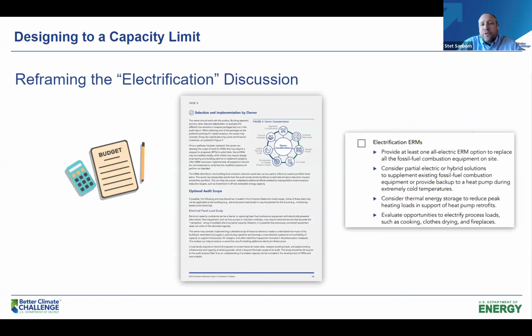And one of the really important ones, and Nora mentioned this, is listed as an optional audit scope of work around the electrical panel. What a lot of folks don't realize is that you may not be using all the capacity that you have on that panel, even if all the breakers are filled up. That's because you may have already gone through a lot of energy efficiency upgrades over the last few years. You might have done an LED lighting retrofit. You might have replaced pumps with VFD controlled pumps in your building. And so you might actually be riding much lower on your capacity curve than you think. You might have additional capacity on that panel, but you won't know unless you do the study.